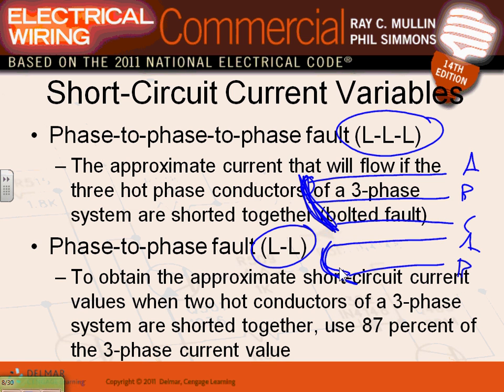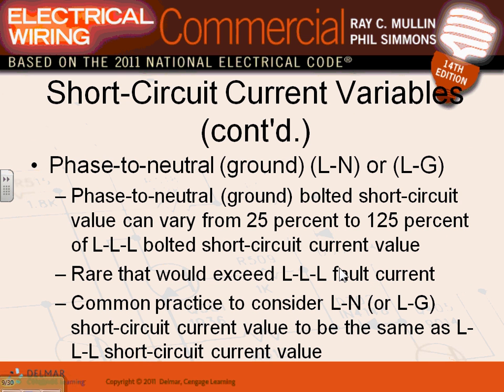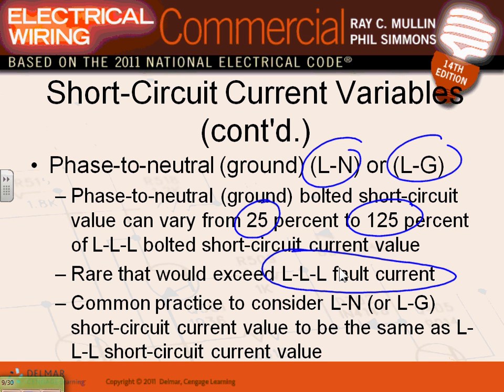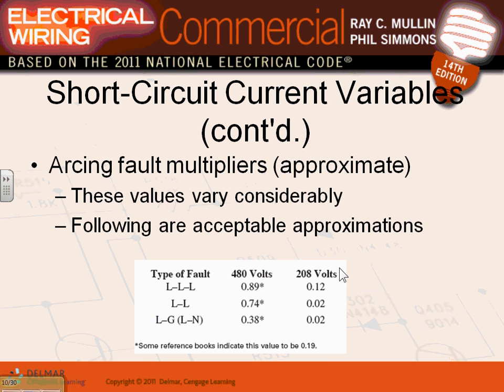If you have line to neutral, Ashley, can you see how you can derate 87%? They're telling you most likely if you have line to line, it's 87% of line to line to line. Line to neutral or line to ground are the same. Usually it goes from 25 to 125. Most engineers assume the default is this one: you calculate based on line to line to line. I would say 95% of the time you're good if you accommodate for line to line to line, because that will cover line to line, line to neutral, or line to ground, all these scenarios that you can get.